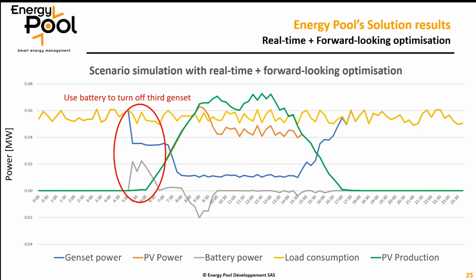If you click one more time, we will see it: we use the battery to minimize the PV curtailment. So from 8 a.m. to around 10 a.m., we use the battery to minimize curtailment of the PV and save some PV generation. But we use this PV generation to charge the battery without touching the operating rules of the gensets, which still cover 20% of the load.